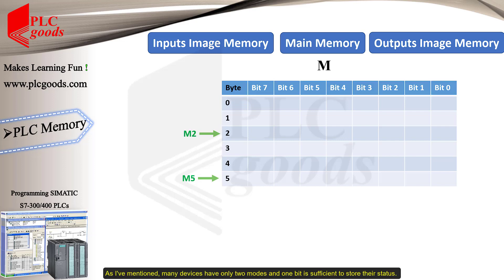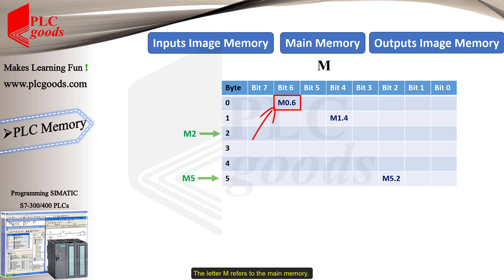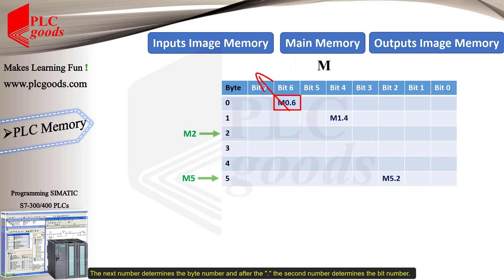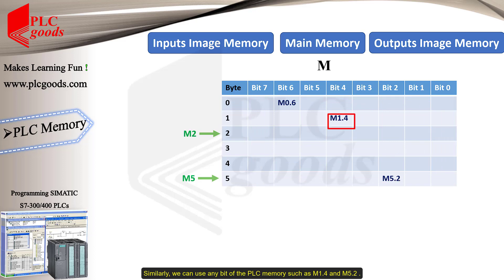As I mentioned, many devices have only two modes, and one bit is sufficient to store their status. For example, M0.6 refers to this location on the main memory. The letter M refers to the main memory. The next number determines the byte number, and after the dot, the second number determines the bit number. Similarly, we can use any bit of the PLC memory, such as M1.4 and M5.2.